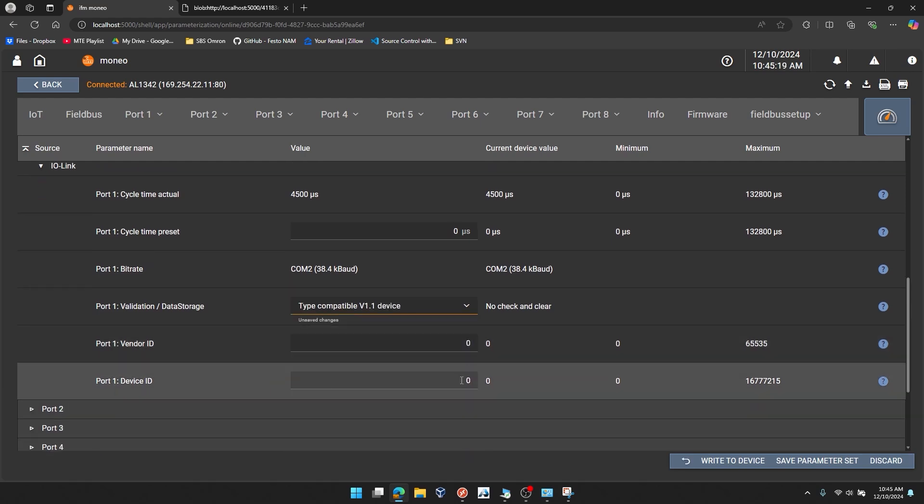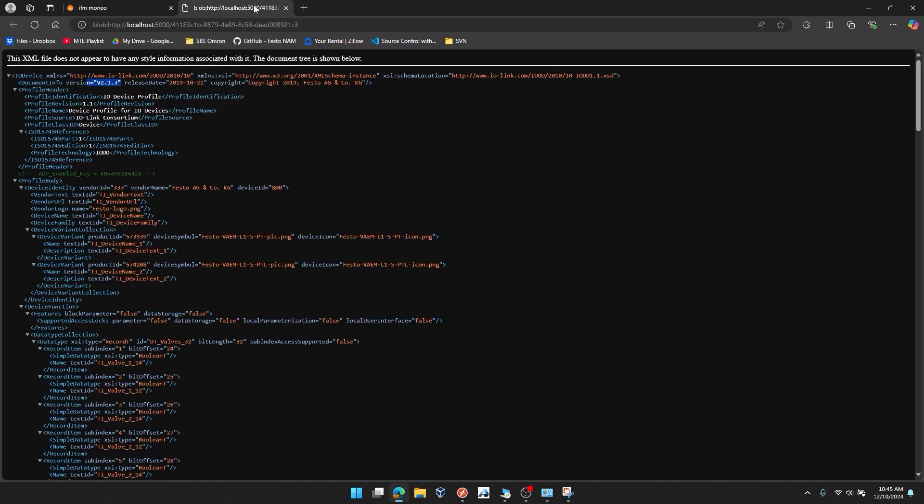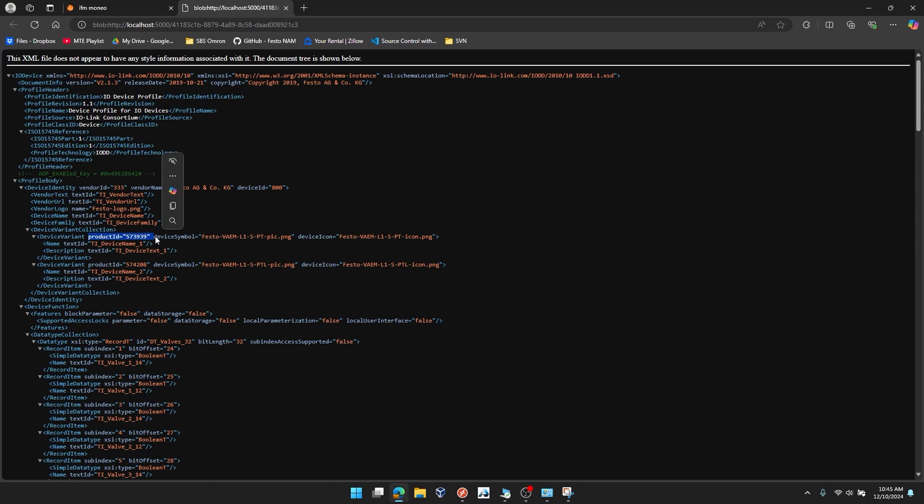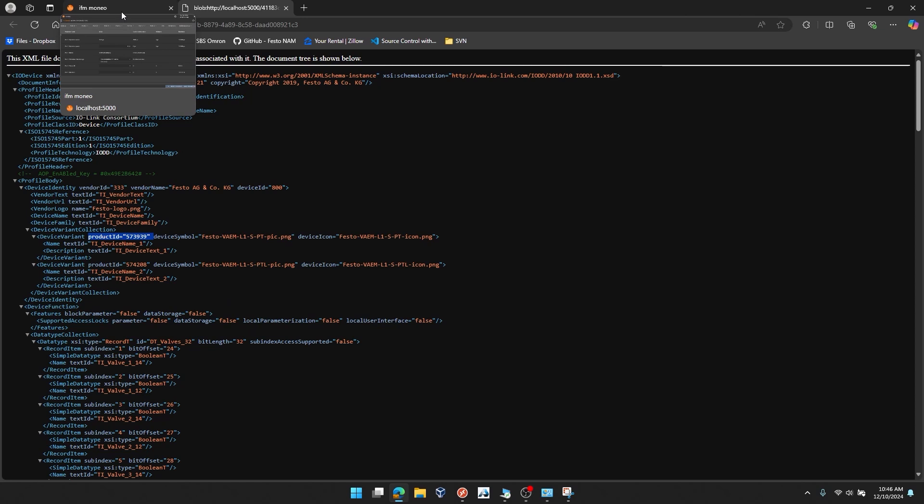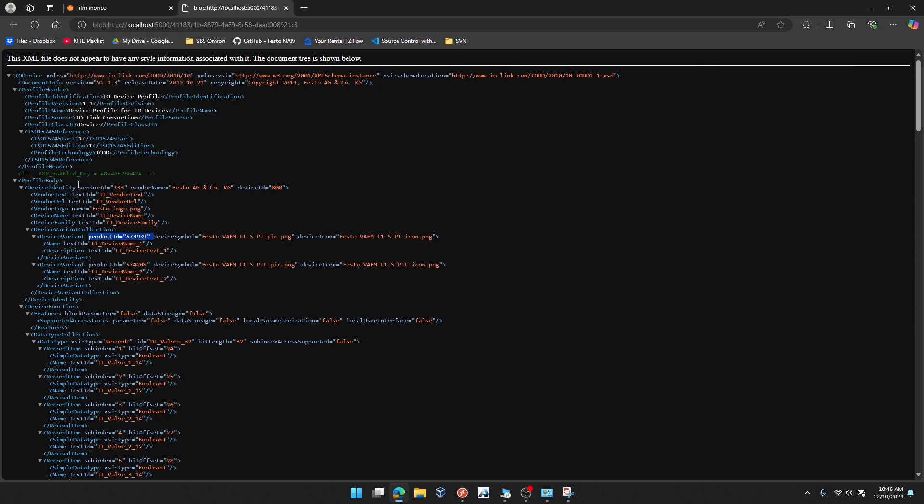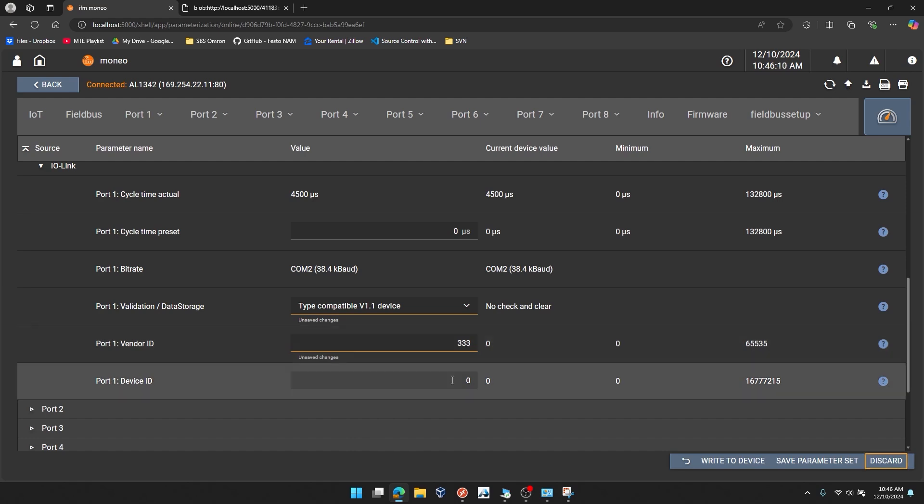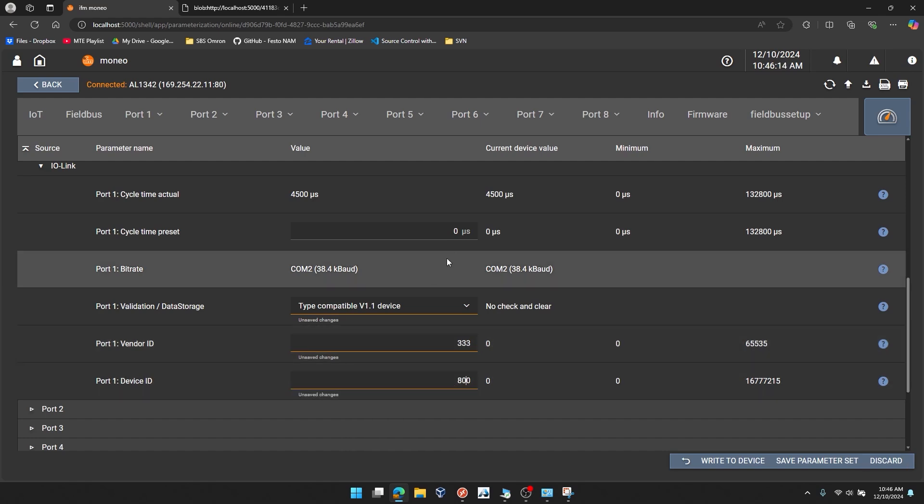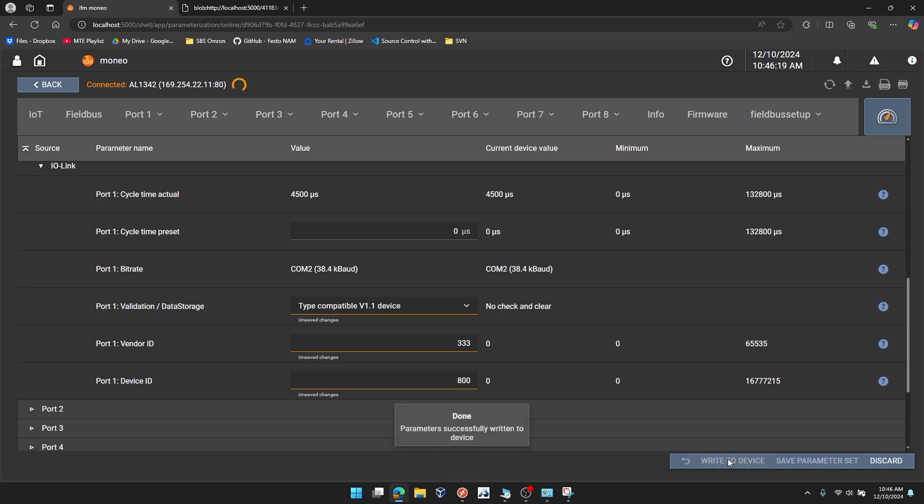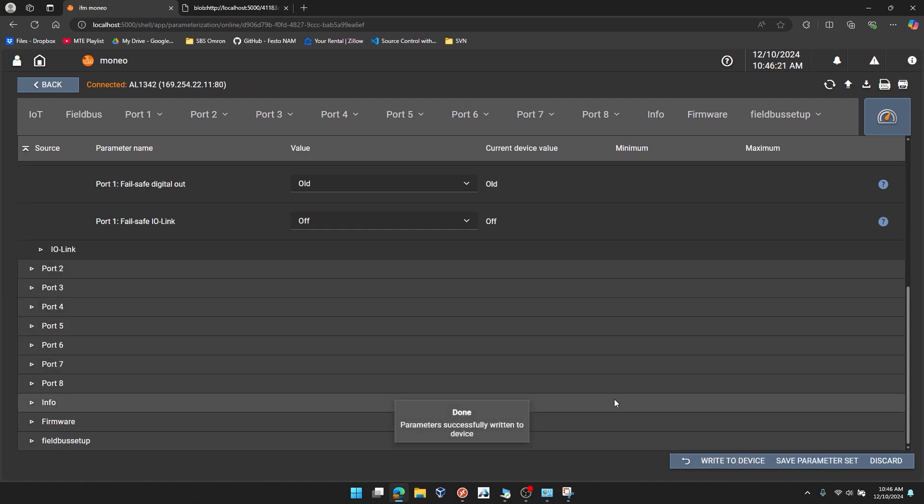And the vendor ID and device ID were also available in the IO-DD file we just expanded. If you look here, the vendor ID is shown right near the top of the profile body. That's 333 and that applies to all Festo devices. Device ID 800 applies uniquely to the VAEM that you're working with here today and the left-hand version of it. If you need to confirm any further, you can look at the product ID shown down here. Product ID is 573939 and you can see that on the top of the IO-Link interface itself. So we're going to take those two decimal values for vendor ID and device ID. And we're going to type them in here.